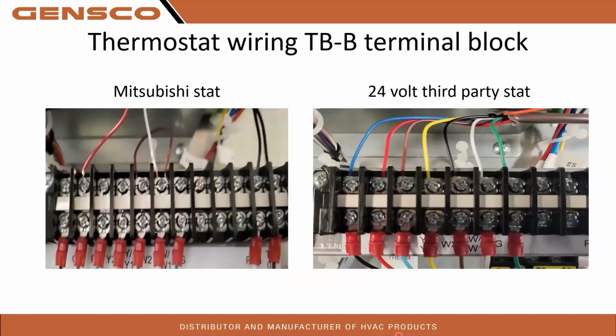Thermostat wiring. So this is terminal block B, TBB. As you can see right here, this is with the Mitsubishi stat. There's my return air thermistor wired in. This is my non-adjustable thermostat. That thing has only got just a couple inches of wire, so you will have to connect onto that with actual thermostat wire. And totally fine there, just like a new construction temp stat.